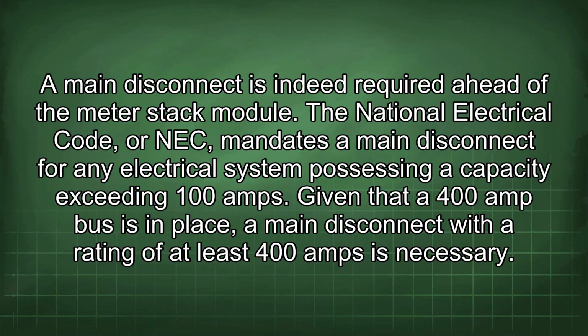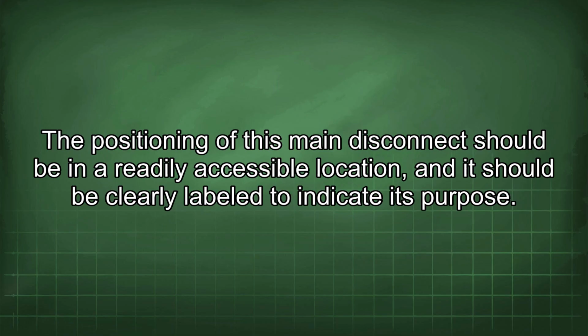Main disconnect is indeed required ahead of the meter stack module. The National Electrical Code, or NEC, mandates a main disconnect for any electrical system possessing a capacity exceeding 100 amps. Given that a 400 amp bus is in place, a main disconnect with a rating of at least 400 amps is necessary. The positioning of this main disconnect should be in a readily accessible location, and it should be clearly labeled to indicate its purpose.